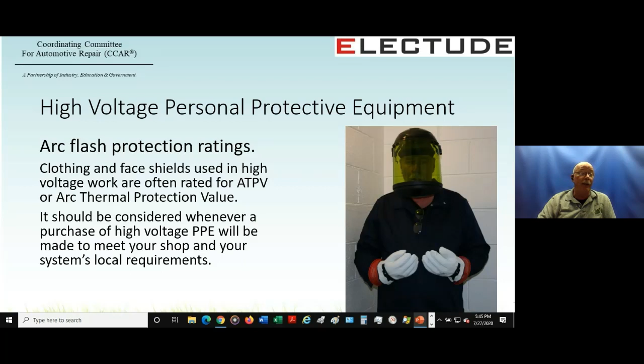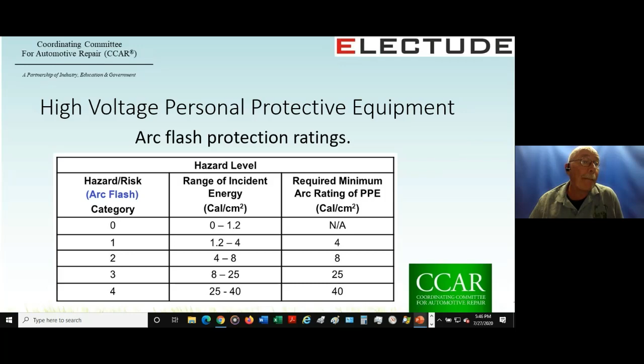Now, this chart shows the arc flash hazard risk category as it relates to incident heat or incident energy, along with the minimum arc thermal protection value for that particular PPE. It must be noted here that the resistance to heat is not the same as electrical isolation. And in the case of education, I think you're going to find out that if you reach up the silo to your administrators and people that deal with safety, they would tell you at the minimum you're going to look at an arc flash category 2. That is a required arc rating of 8 calories per square centimeter. We'll get to that in a second.